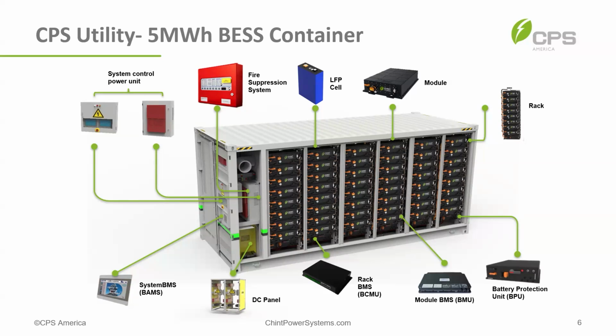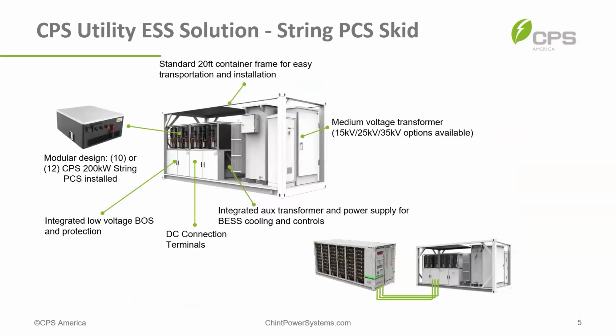One nice thing about how we have this set up is we want to get as granular as possible, we want to see everything. Inside each module we have CSC sensors, so we can see individual cell temperature levels, voltage levels, and everything like that. That data is brought down to the BMU, and then down to our BCMU. Don't worry about the acronyms - essentially, from our module level view we take all that data and say this rack with these 8 modules is doing this as a whole, and that goes to our battery management system, which talks with our PCS and the EMS.